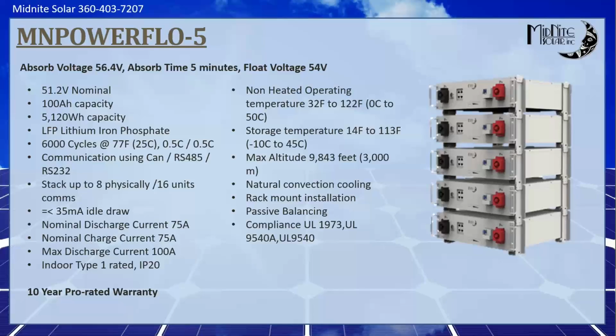So what happens in closed loop, just as a quick backup and give you a bit of an overview, in closed loop, the battery controls the charging. The first thing it's going to do is tell the inverter, hey, I am X many amp hours. So that stack you see sitting there of 5 batteries, it would tell the inverter, I'm a 500 amp hour battery bank. I have a 400 amp charge current limit, and the inverter would program that in. And then it tells it what it wants to charge to and when it wants to stop charging, if you will.